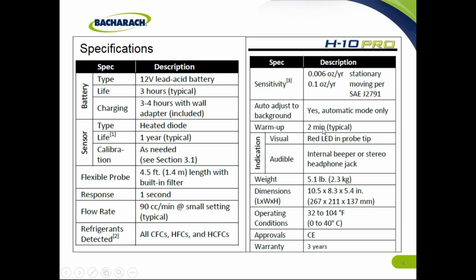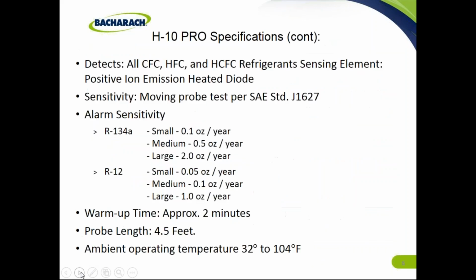And there are 2 indications of a leak. One's visual, where you have a red LED in the probe tip, which will flash faster with the leak. And then you have an audible sound. Usually you have a tick rate that is between 1 and 3 ticks per second. As you get closer to a leak, it'll tick a lot faster. So the light will flash in the probe and the audible alarm will tick faster. It weighs 5.1 pounds. There are dimensions. You operate it between 32 and 104 degrees. It has a warranty of 3 years, which does not include the sensor.